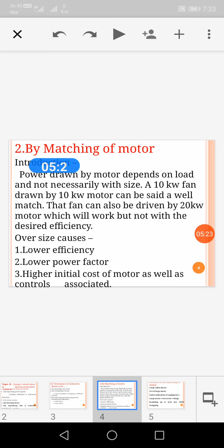Reasons for mismatching of the motor: a large safety factor and use of a large motor, underutilization of equipment, a large motor even at low voltage, and rounding up to the next size while designing. However, a suitable oversize margin offers an advantage. What advantage? Spare capacity in case of future expansion and accommodation of expected additional load, and that's why we keep this margin in the motor.